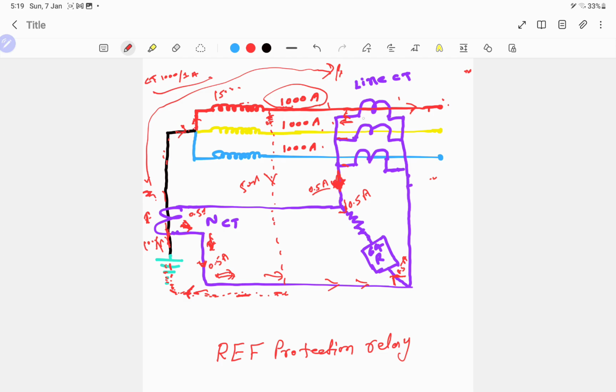Because all three phases are balanced here and the CTs will sense the 1000 amps, the resultant current of the secondary winding of all the line CTs will be 0 amp. So there will be no current flowing through the secondary winding here. But here, where the fault occurs at the winding, the current will assume the 500 amps, the same fault current. The 500 amp fault current is flowing from the secondary winding through the ground, through this neutral CT, and going towards the neutral point of the transformer LV winding and through the R phase winding.